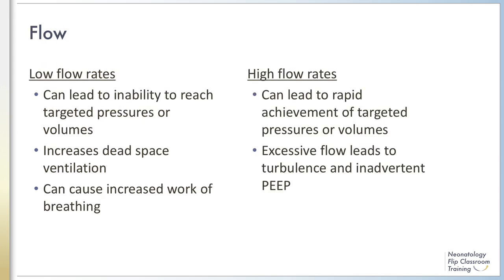Flow refers to the amount of gas circulating through the ventilator during a given amount of time — in other words, the rate of gas delivered in the ventilator circuit. Flow rates are set by the clinician, and usually 6 to 10 liters per minute is sufficient. This parameter is generally not adjusted during ventilation. Peak flow rate is the maximum flow rate delivered by the ventilator during an inspiration, and is used to deliver the set pressure or volume.